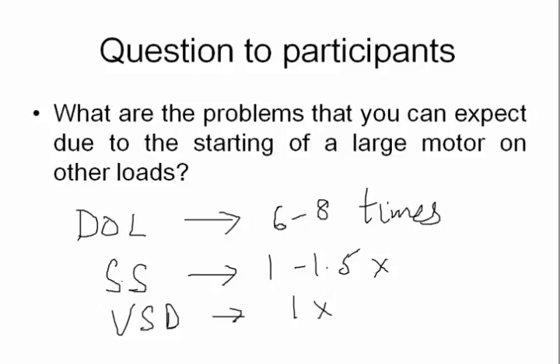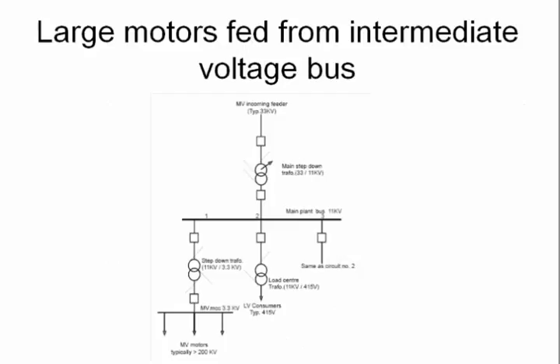We also have other starting methods, auto transformer starting to reduce the voltage. You have star delta starter, which also applies the star voltage. And they can give you anywhere from 3 to 4 times starting current. So large motors are fed from an intermediate voltage bus, directly fed from 11 kV so that your voltage dip is lower. So you might have different voltages for different motors, different ratings.